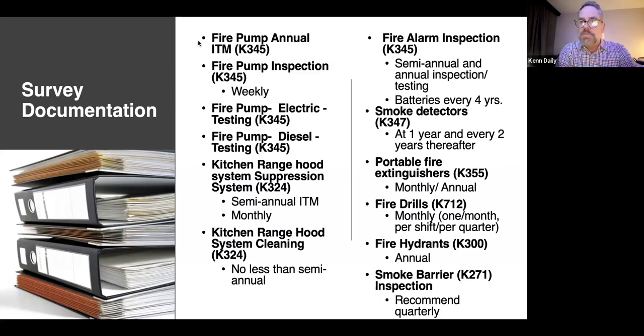Fire drills, 1 per month, per shift, per quarter, to 12 fire drills a year, varied times under varied conditions, varying the times no less than 1 hour apart. I know in Pennsylvania you also have your annual fire drill monitoring or audit by an outside contractor or fire official to ensure that your staff is well prepared to do that or are doing it correctly.